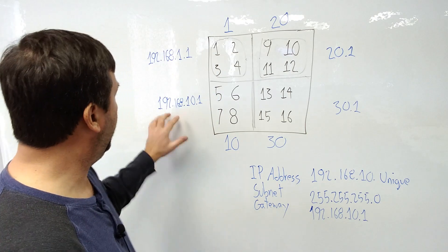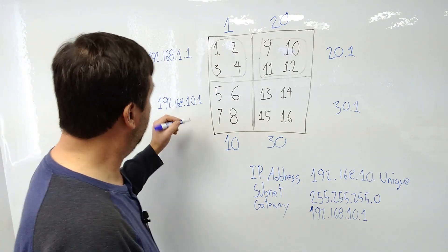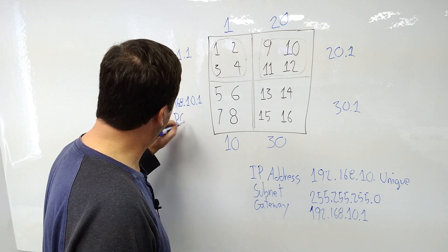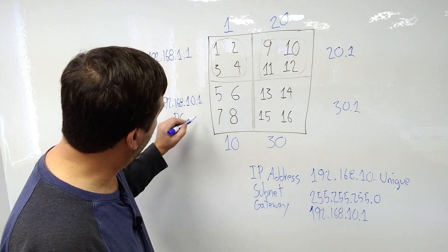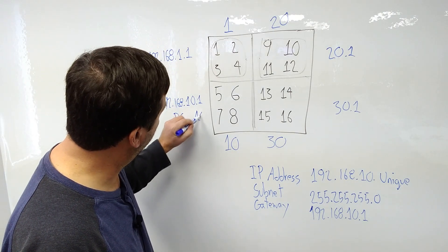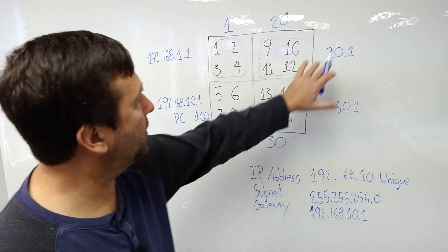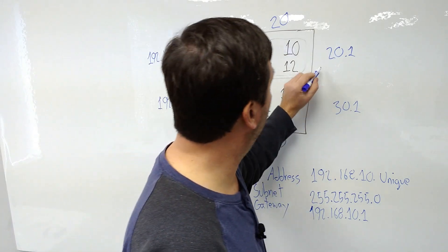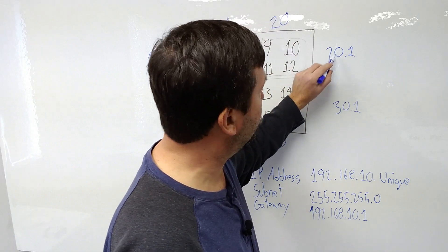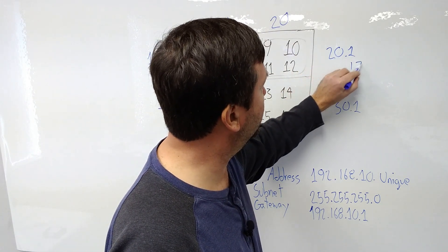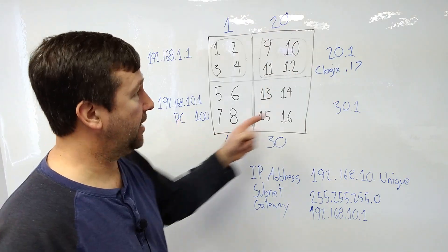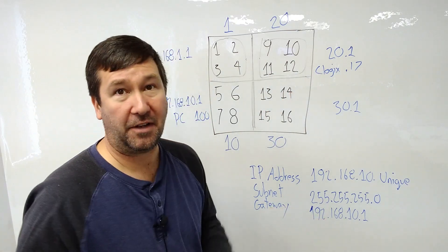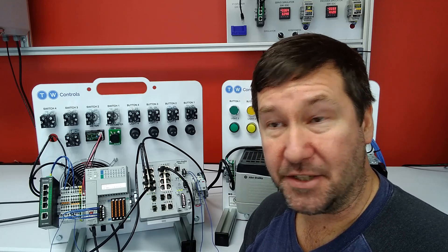So in this case, let's say my IP address of, well, we'll just call it, let's just use our PC is 192.168.10.100. And I want to communicate with that control logix, which was 192.168.20.17. I can actually communicate between these two using this default gateway. Now that we see why we may use a VLAN, let's put it into a practical application.